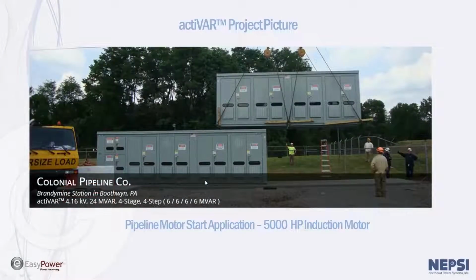Here's a picture of a 24 megavar system that went to Brandywine Station in Pennsylvania. It consisted of 4 stages of 6 megavars. It was designed to assist with the starting of 2 5,000 horsepower induction motors at a pump station for a pipeline application. So the pieces are shipped on a flatbed truck and lifted by crane and put into place. Essentially connect the bus bars up, connect some control wiring up between the stages, and this system is ready for operation.